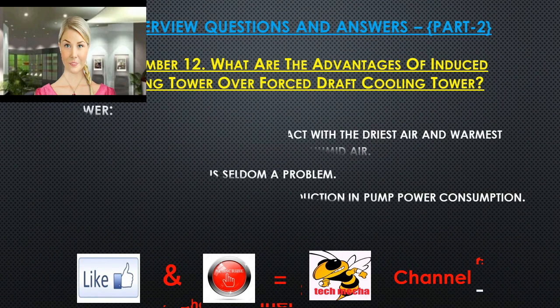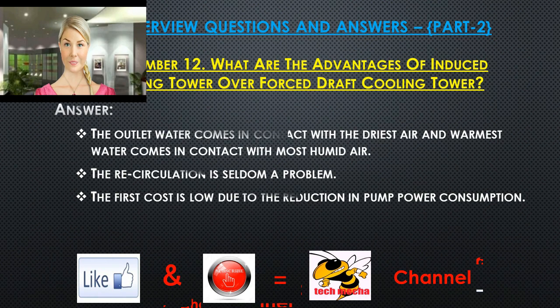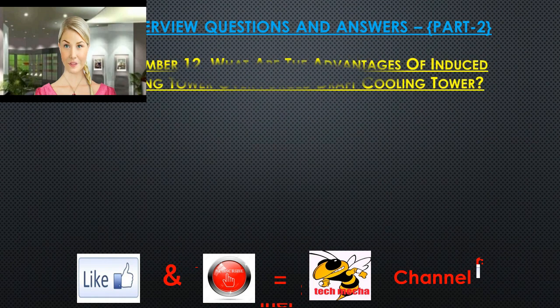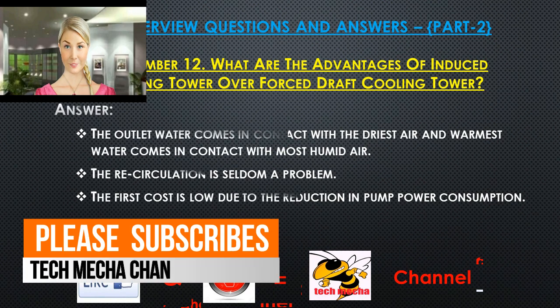Question 12: What are the advantages of induced draft cooling towers over forced draft cooling towers? The outlet water comes in contact with the driest air, and the warmest water comes in contact with the most humid air. Recirculation is seldom a problem, and the first cost is low due to reduction in pump power consumption.